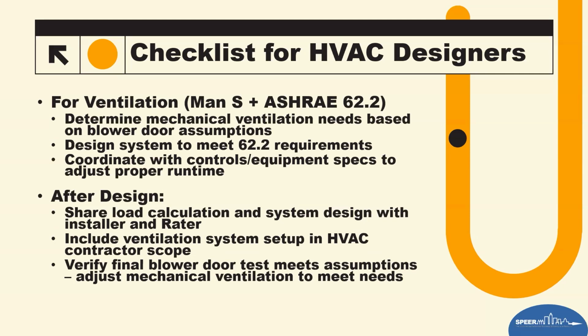And then, of course, after the design, when you go for a final and the third party's in there testing the mechanical ventilation, which is now required for Energy Star and 2021 moving forward. Once you do that, you share that load calculation and the HVAC design with the installer and the rater. You include the ventilation system setup in the HVAC contractor's scope of work.